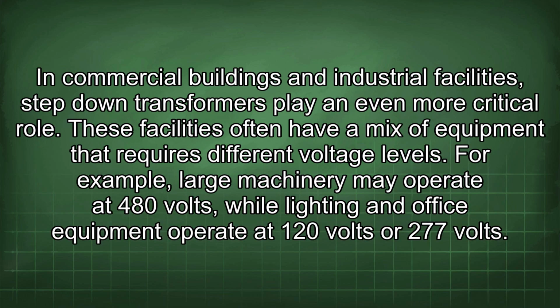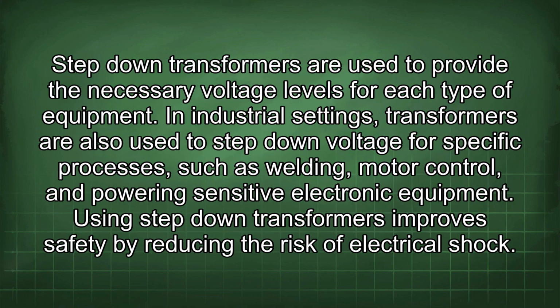In commercial buildings and industrial facilities, step-down transformers play an even more critical role. These facilities often have a mix of equipment that requires different voltage levels. For example, large machinery may operate at 480 volts, while lighting and office equipment operate at 120 volts or 277 volts. Step-down transformers are used to provide the necessary voltage levels for each type of equipment. In industrial settings, transformers are also used to step down voltage for specific processes such as welding, motor control, and powering sensitive electronic equipment. Using step-down transformers improves safety by reducing the risk of electrical shock.